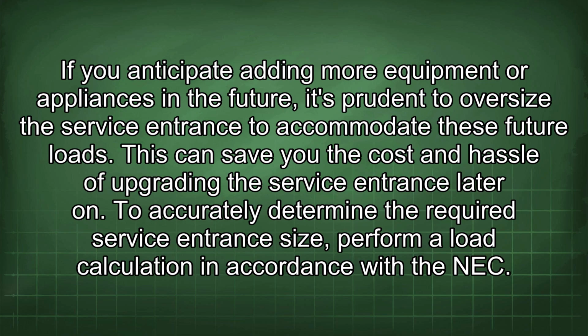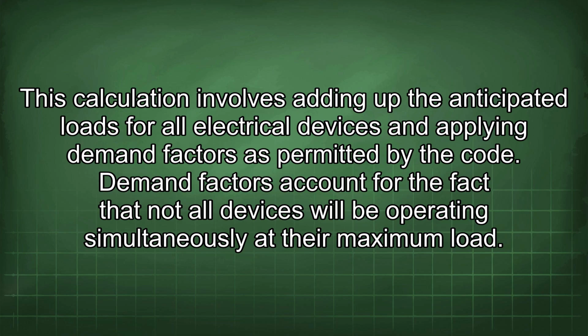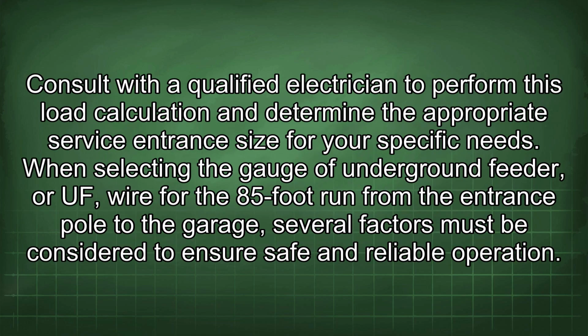To accurately determine the required service entrance size, perform a load calculation in accordance with the NEC. This calculation involves adding up the anticipated loads for all electrical devices and applying demand factors as permitted by the code. Demand factors account for the fact that not all devices will be operating simultaneously at their maximum load. Consult with a qualified electrician to perform this load calculation and determine the appropriate service entrance size for your specific needs.